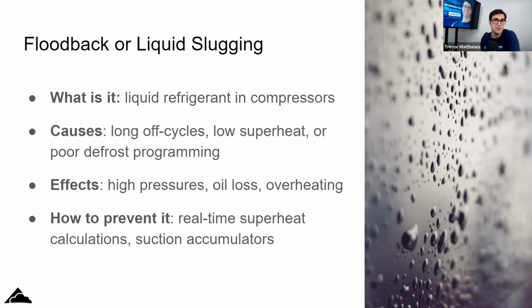Yeah, so it all depends on the application. If we talk about CO2 refrigeration, it's being done there, and in standard synthetic racks it's still happening. A lot of the things that you can check for flood back, for example, the big one's airflow. You can measure the airflow. You can measure the oil pressure differential, because if you start to lose oil pressure differential, you could be washing it out with refrigerant. It could be something else, but it's a good sign that it could be flood back that's happening there.